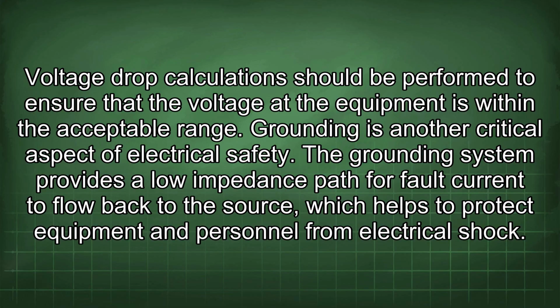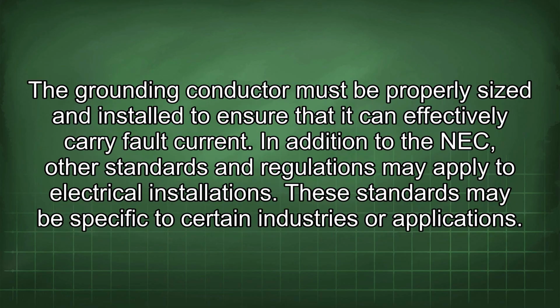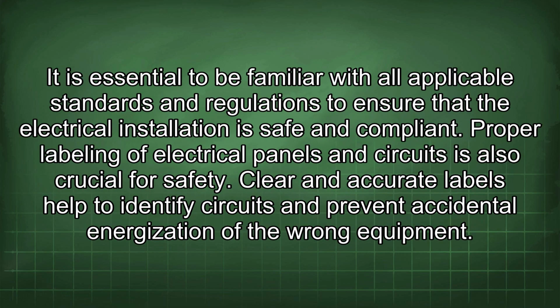Grounding is another critical aspect of electrical safety. The grounding system provides a low impedance path for fault current to flow back to the source, which helps to protect equipment and personnel from electrical shock. The grounding conductor must be properly sized and installed to ensure that it can effectively carry fault current. In addition to the NEC, other standards and regulations may apply to electrical installations. These standards may be specific to certain industries or applications. It is essential to be familiar with all applicable standards and regulations to ensure that the electrical installation is safe and compliant.